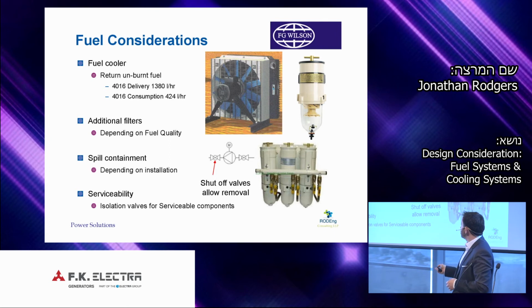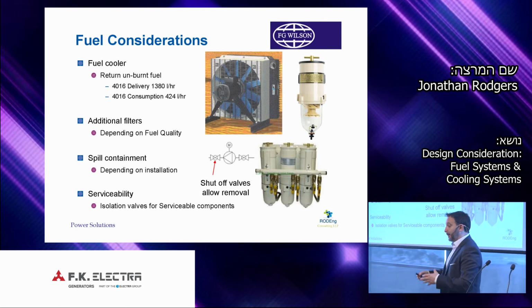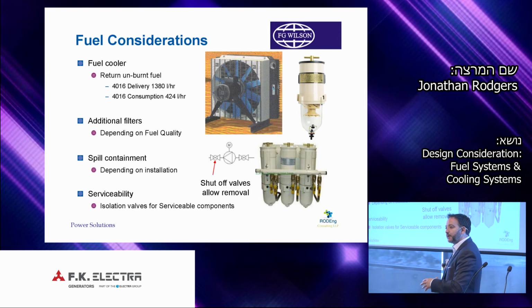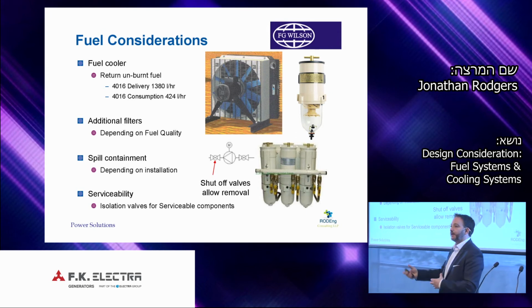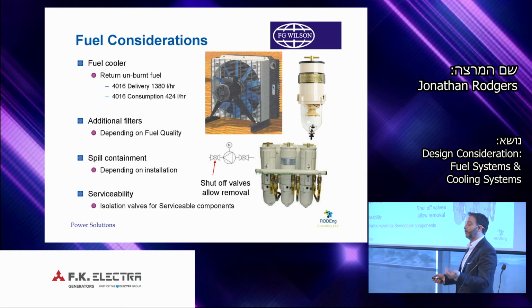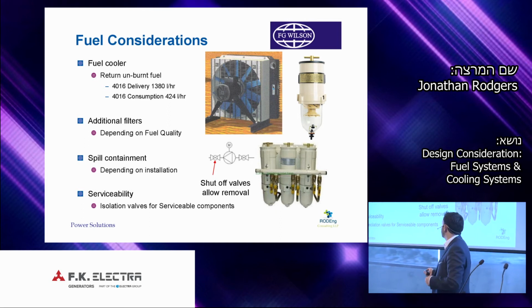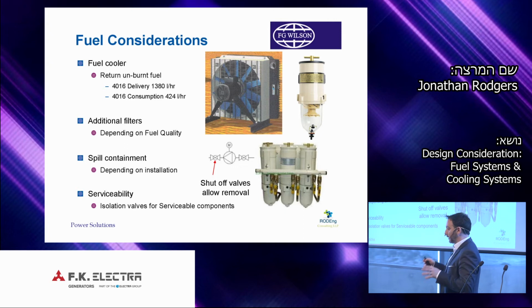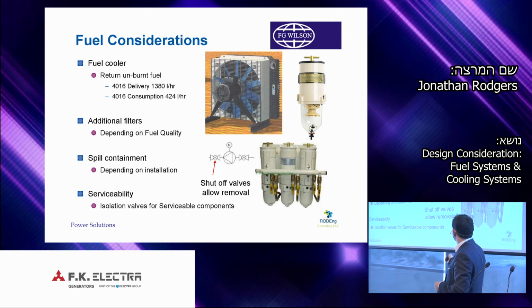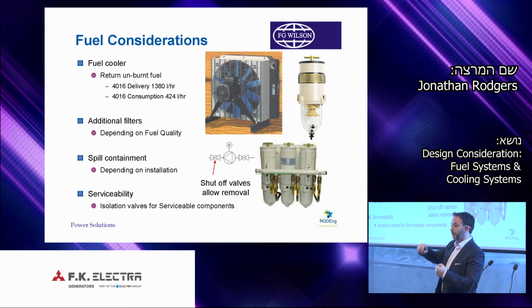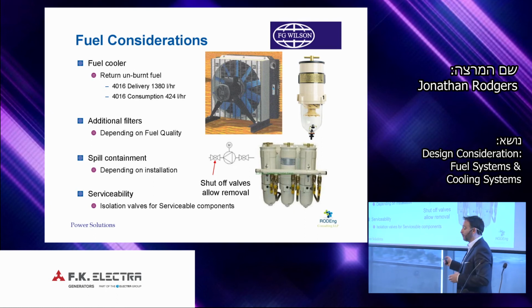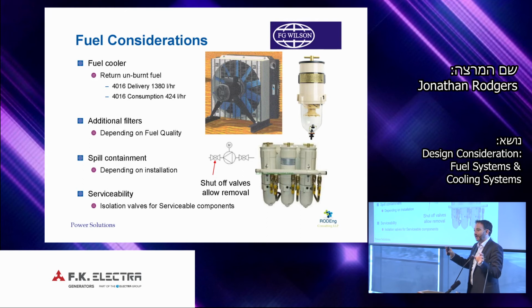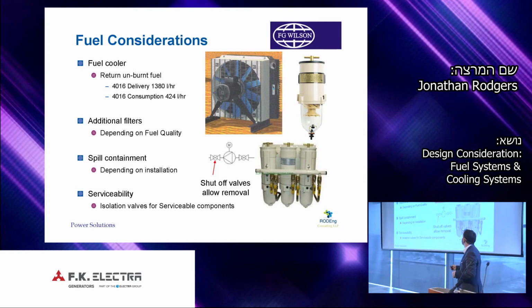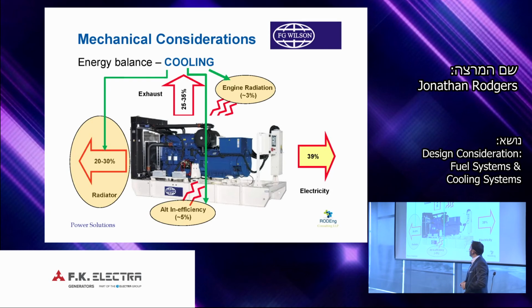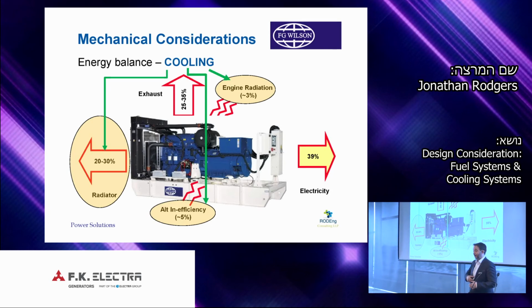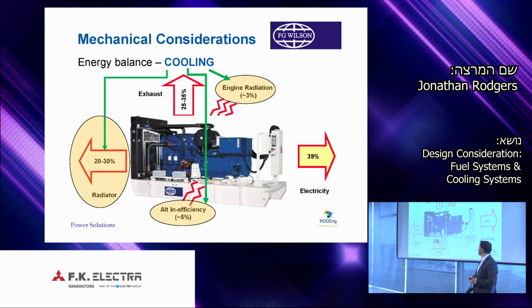With all of these arrangements, we need to look at any spill containment. So we will have trays underneath. We contain any spill, contain any possible area of leak, and we try to signal an alarm for any leak. And again, we think of serviceability. So this is where with multiple units, we can isolate and remove. We have the same with pumps. Again, it's the isolation, being able to have isolation valves. So that was fuel and how we supply all of our fuel to the unit.